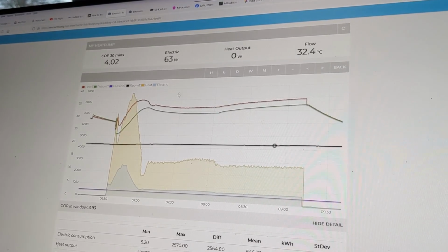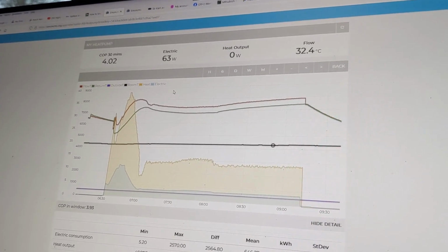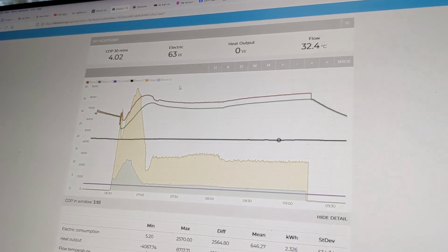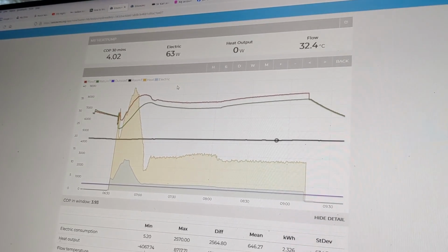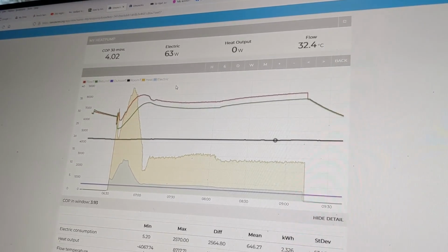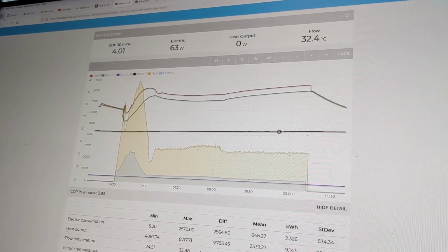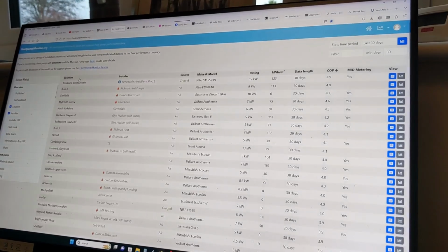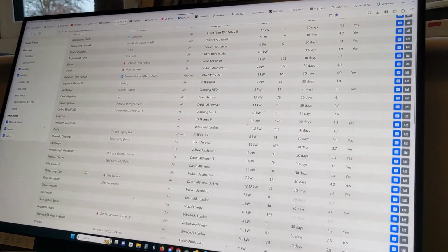Just pick a couple of slots and ask, is it achieving what the heat pump says it should? For that heat pump, because otherwise it depends so much on the weather. And also with this open monitor system, you can go and look at other people's heat pumps performing in a similar situation, and even compare the same model as your heat pump. If it's performing drastically worse than somebody else's, you can go back and investigate.